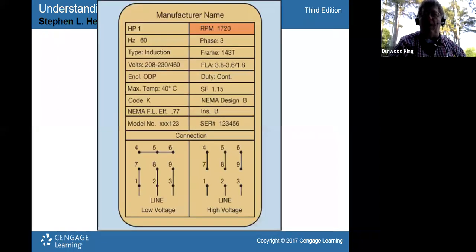And the next part of your nameplate would be the RPM. That's going to be how many revolutions per minute that it'll turn. So in the range of 1720 is typical, but sometimes you'll see a 3450 like on blowers. So if you got a blower motor for an air blower, it may be double that. But most of them for production equipment are usually around 1720, 1725, somewhere in that range. Or so close to it.